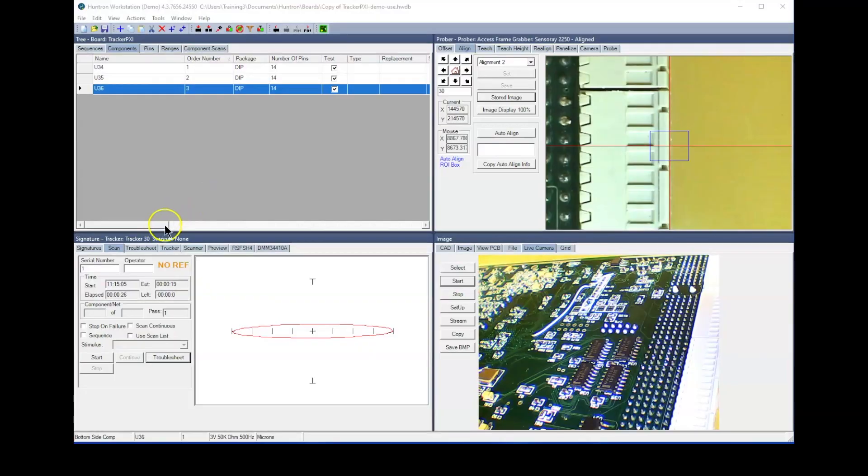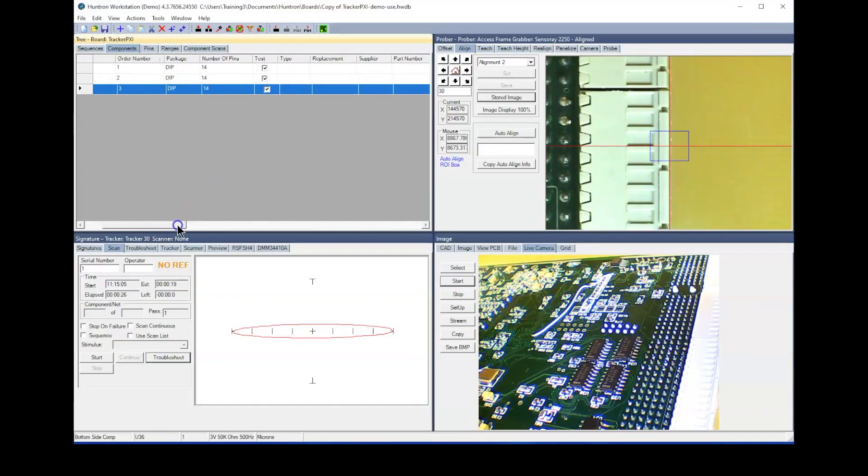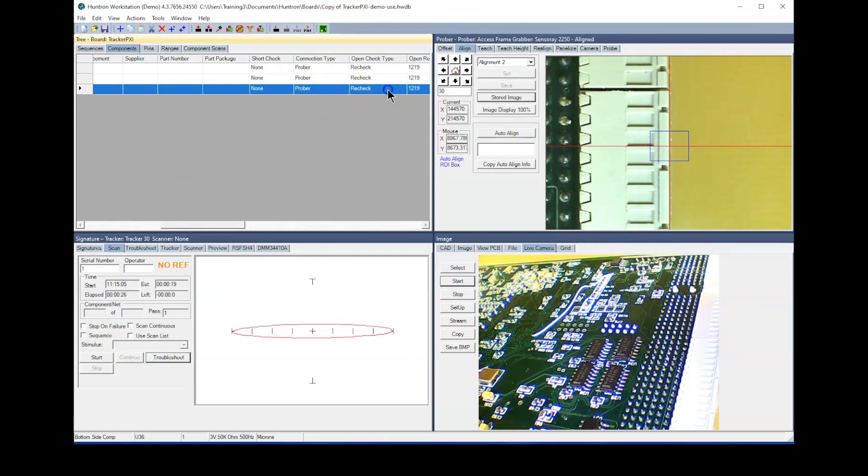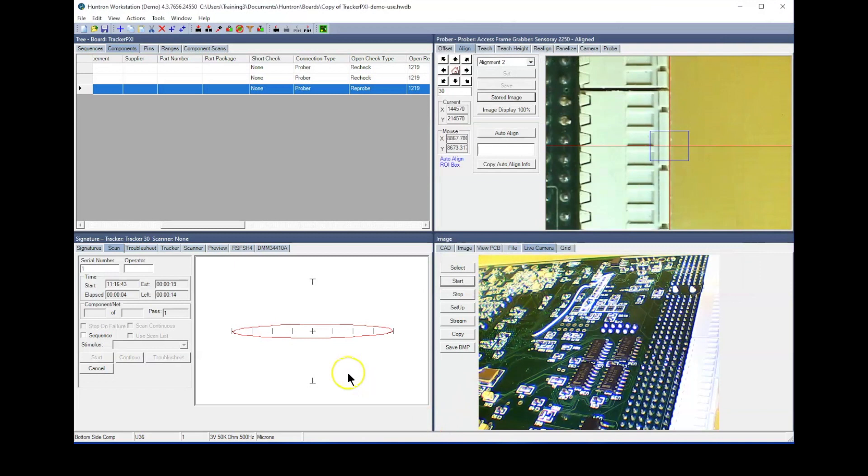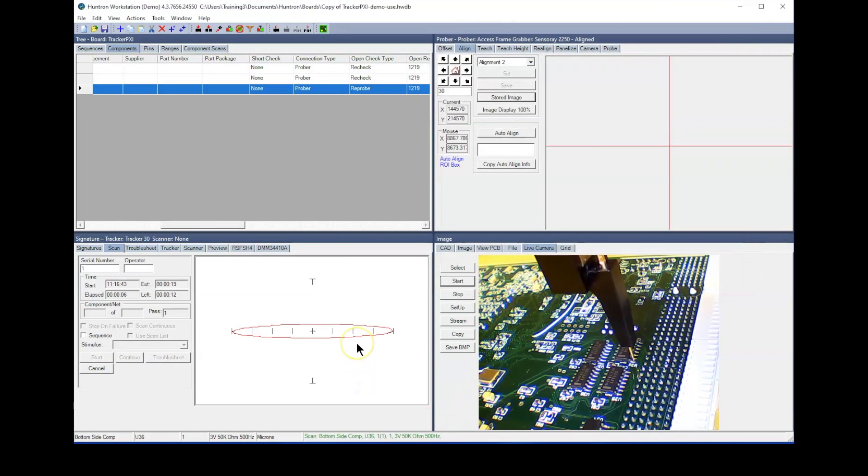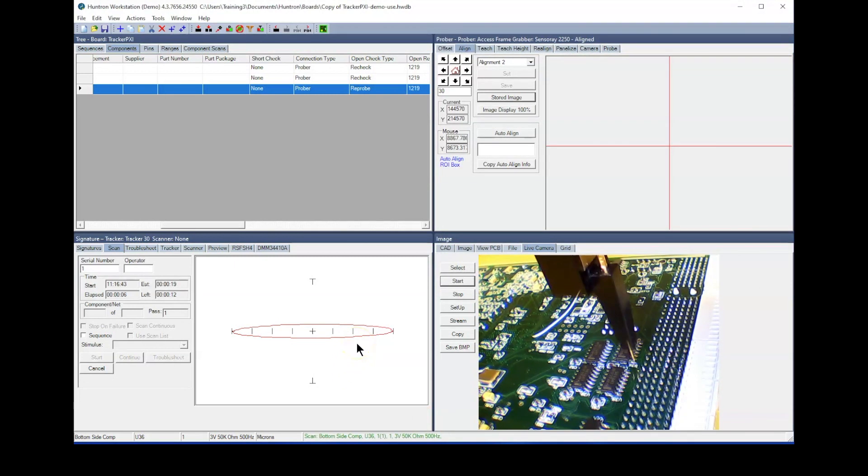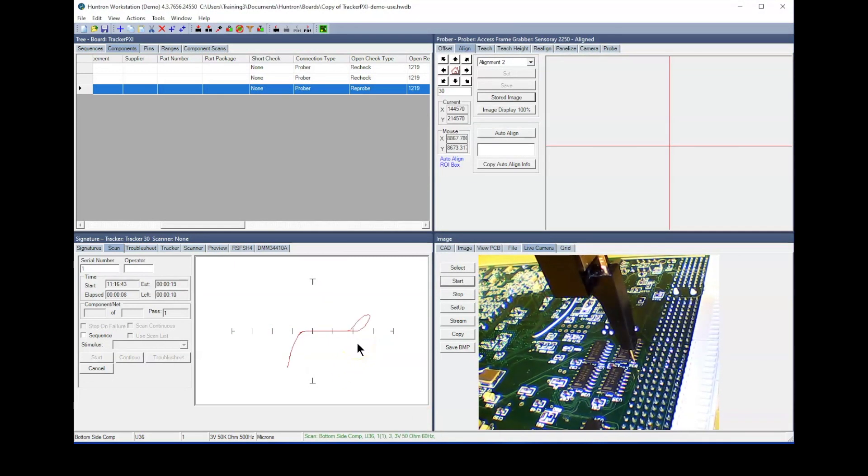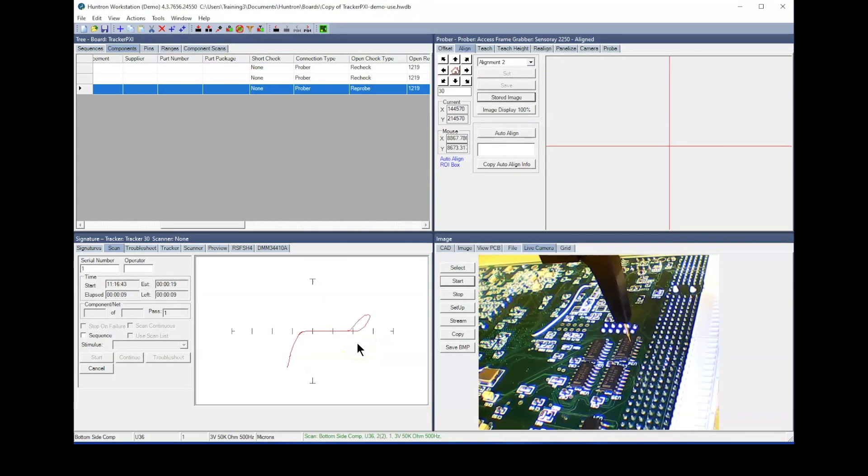The other setting for open check type is Reprobe. When Reprobe is selected, the probe will raise and lower several times and then try to capture the signature. The idea is that by probing the same spot several times, you will eventually get through the coating.